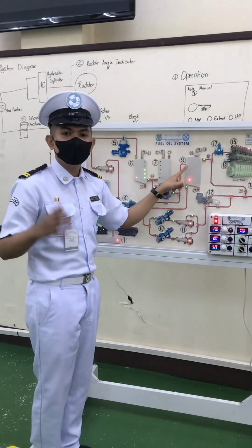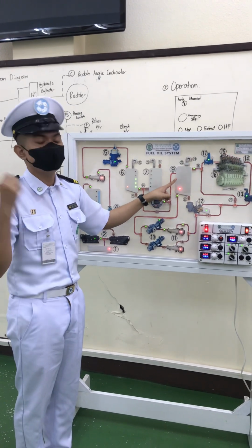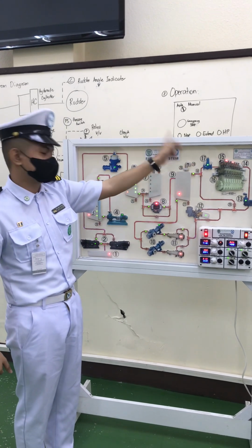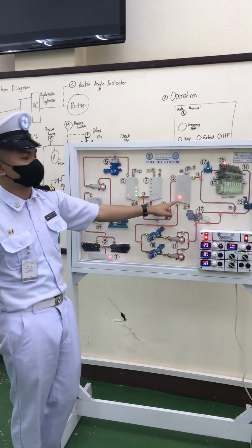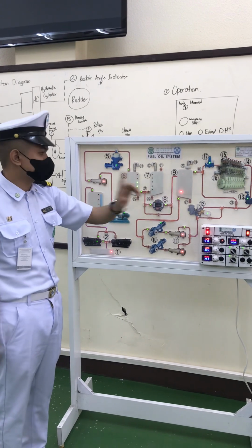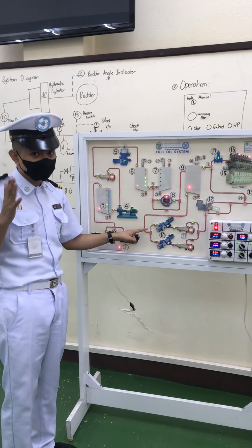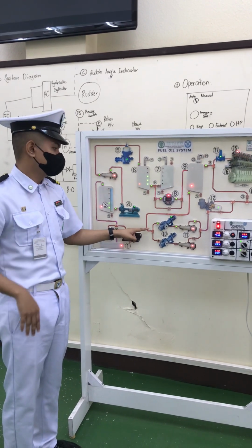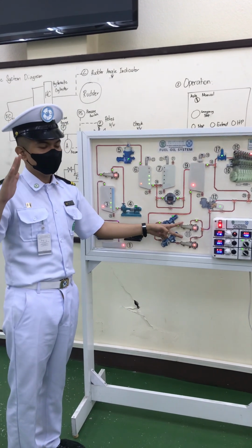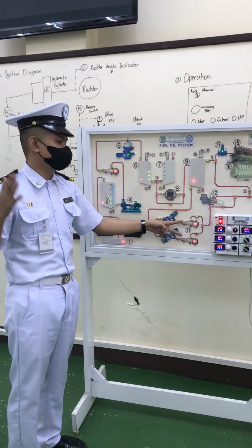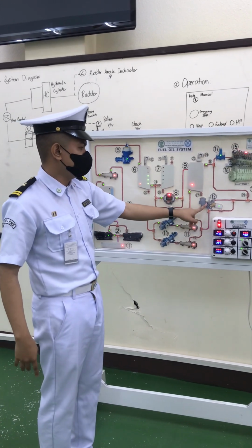From the mixing tank, it is where these two different fuels, the diesel oil and fuel oil, will be mixed. Here again, there is a vent for exhaust gas and another drain valve in case of presence of contaminants. Once mixed, it will go down to the booster pump, which boosts the pressure of the fuel oil. Once done, it will go to the heater to increase the temperature to have the correct viscosity. Then it will go to the viscosity regulator.